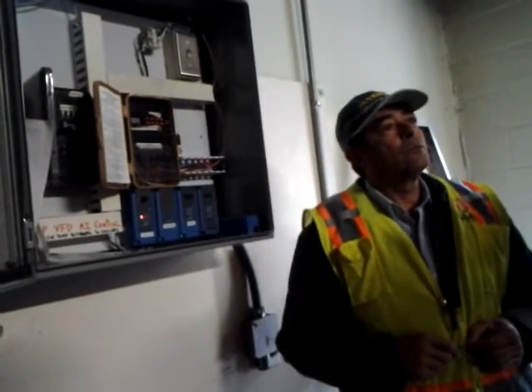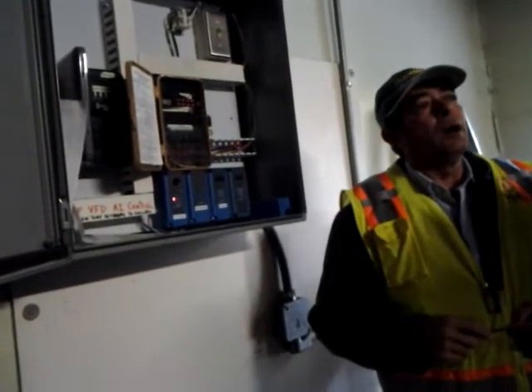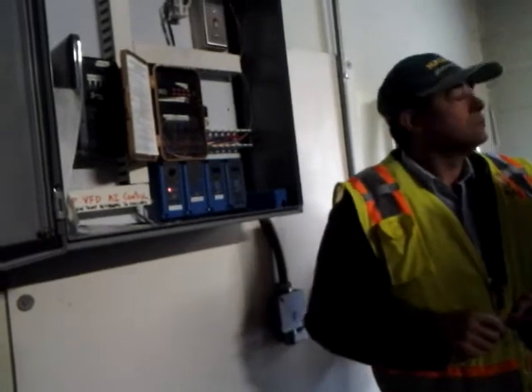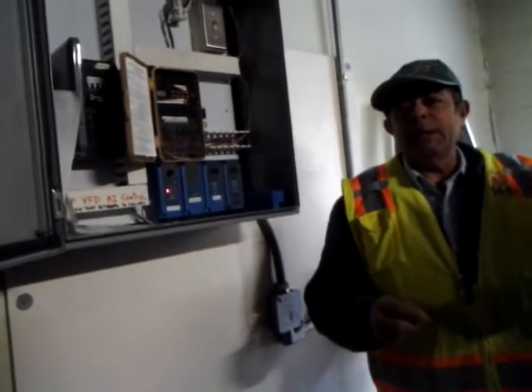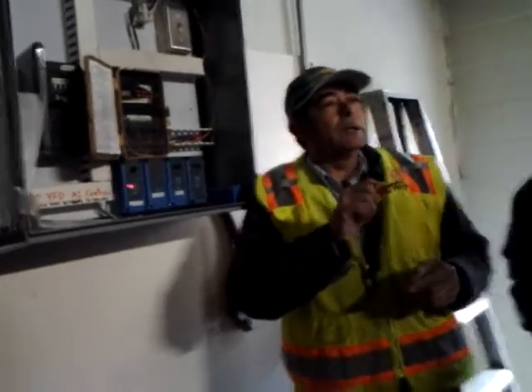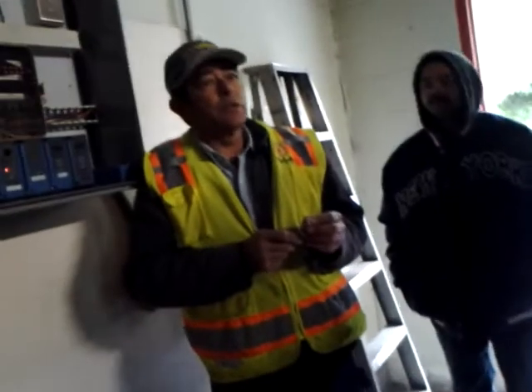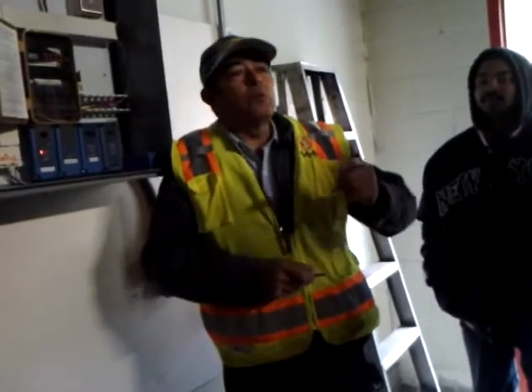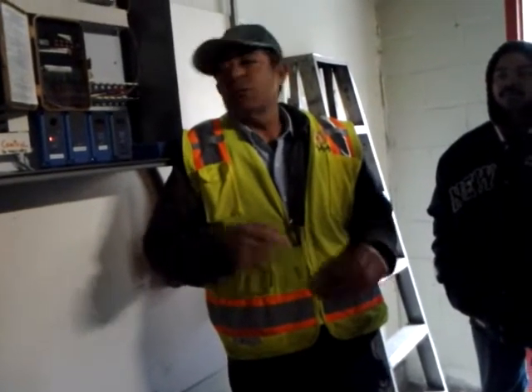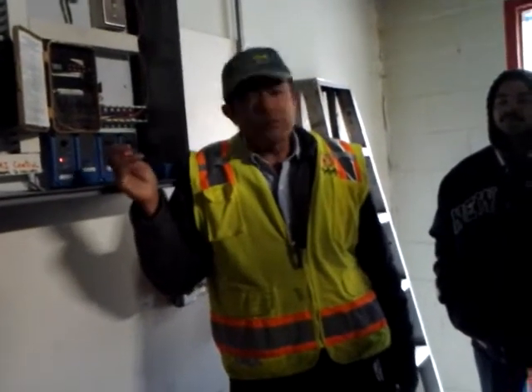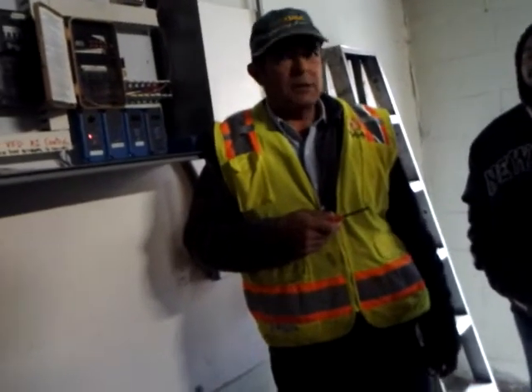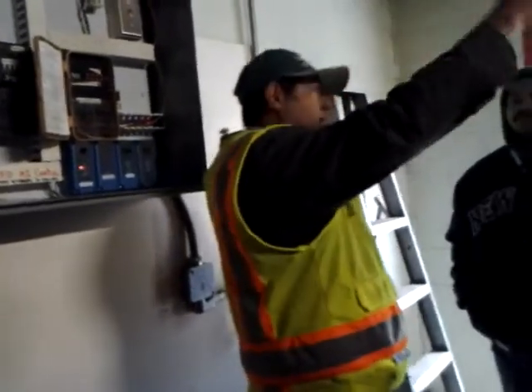You're saying that it turns it into like a DC motor that you can slow down? Slow down the motors? Yes. You probably know that, like in the States, we work with 60 hertz. If you reduce the amount of hertz, you reduce the speed. Right. So that's the way the variable frequency drive works. All it does is send an electronic signal to that thing to tell it how to operate. So very simple. If you guys, let's go through that door. I'll show you guys the cooling tower.